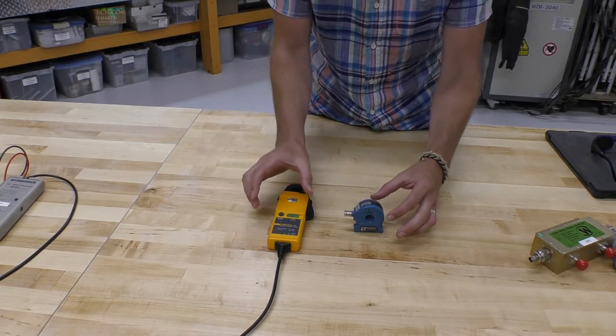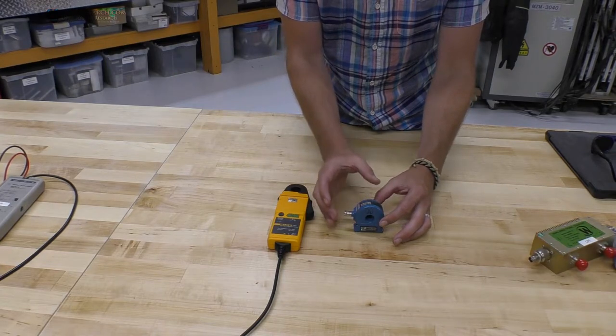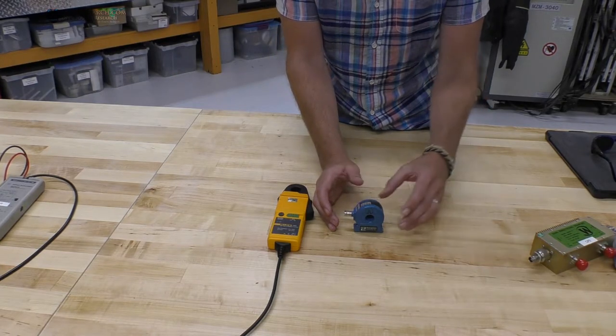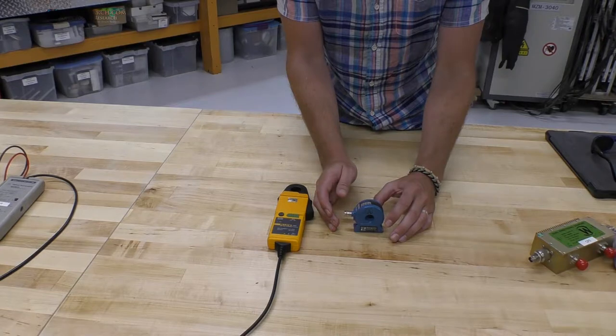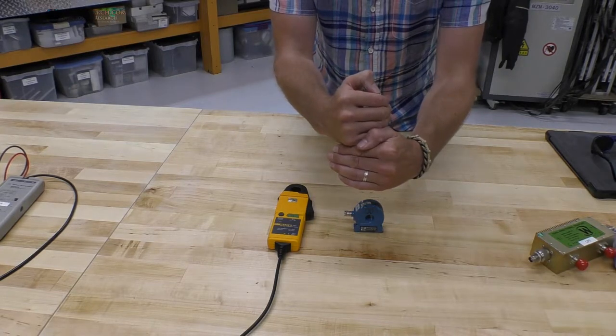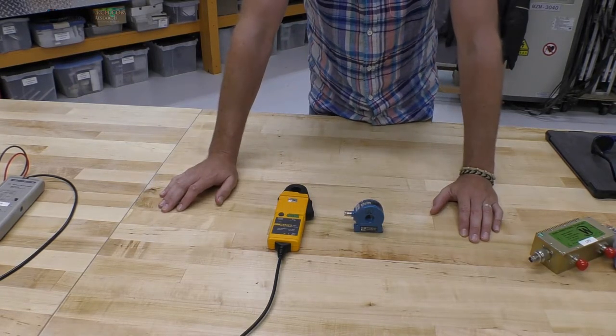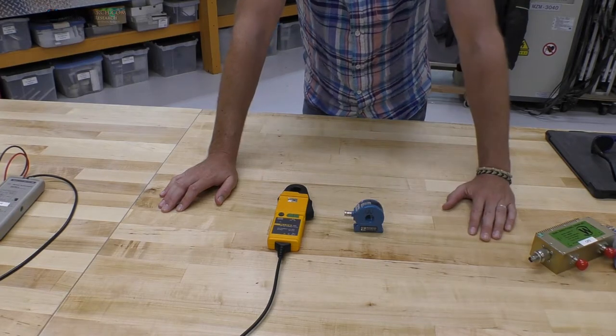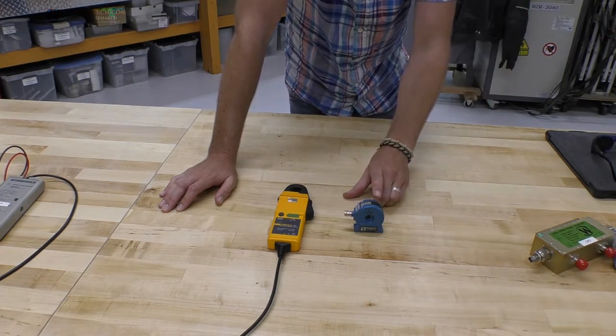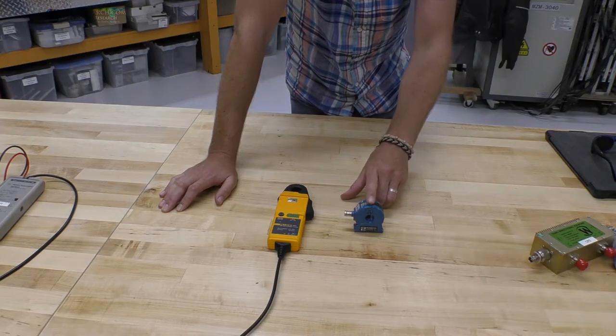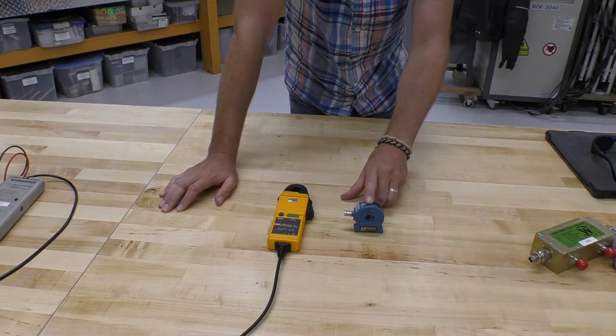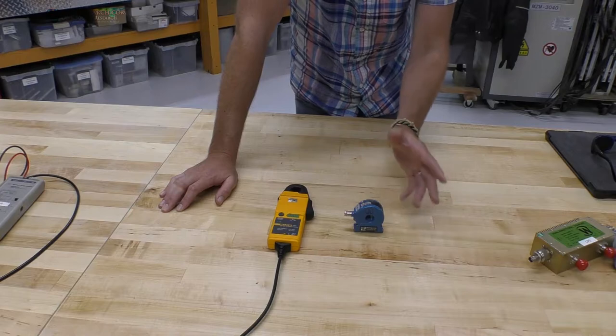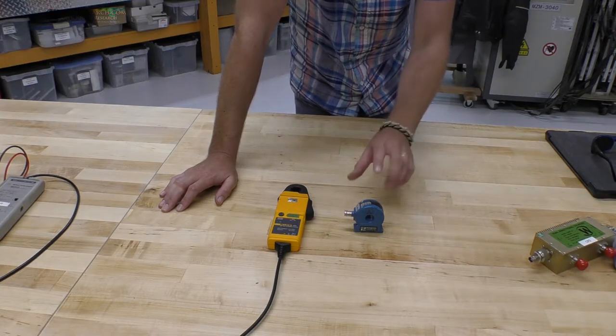In other words, when I put voltage and current across the resistive element within the thermal power probe, there is zero degrees phase difference between the voltage and the current for this particular probe up to 10 megahertz, so you know that whichever system that you're measuring, this probe will be good up to 10 megahertz from about 100 kilohertz, 10 kilohertz.